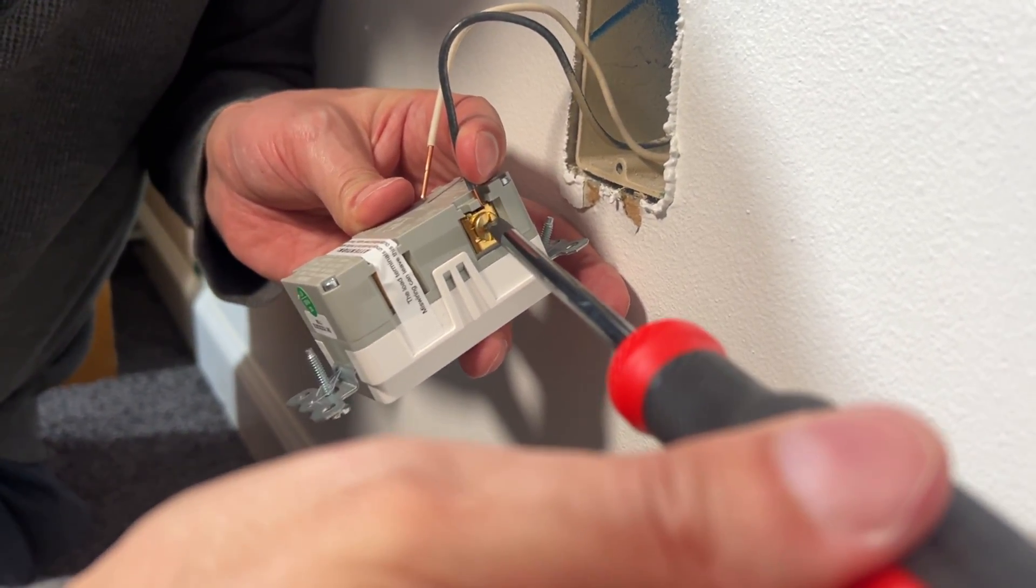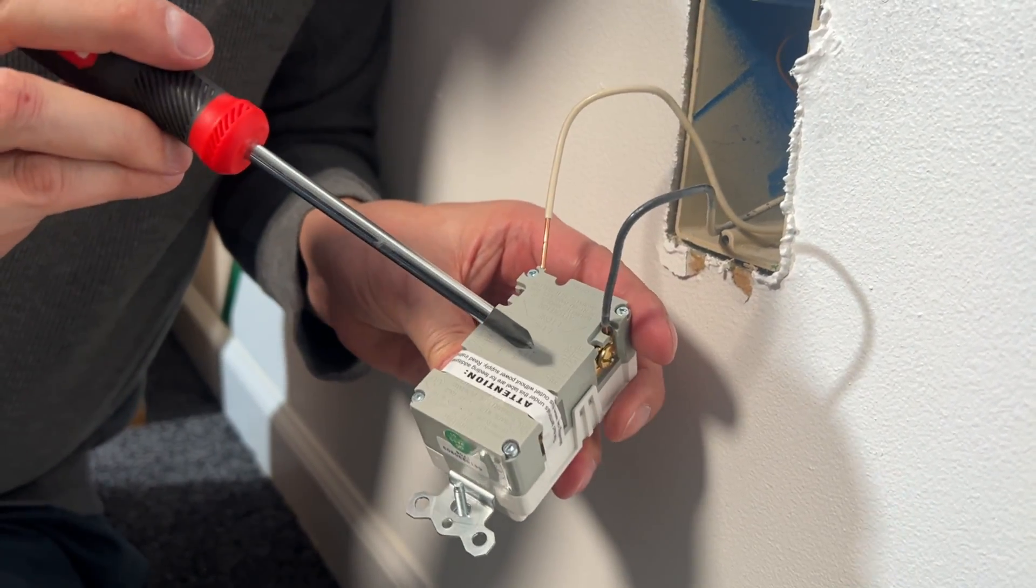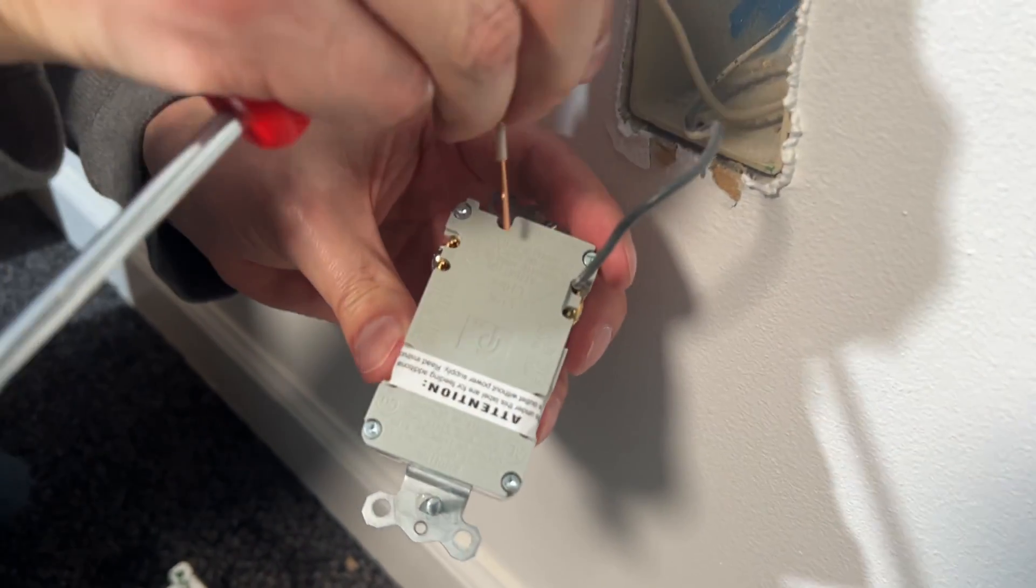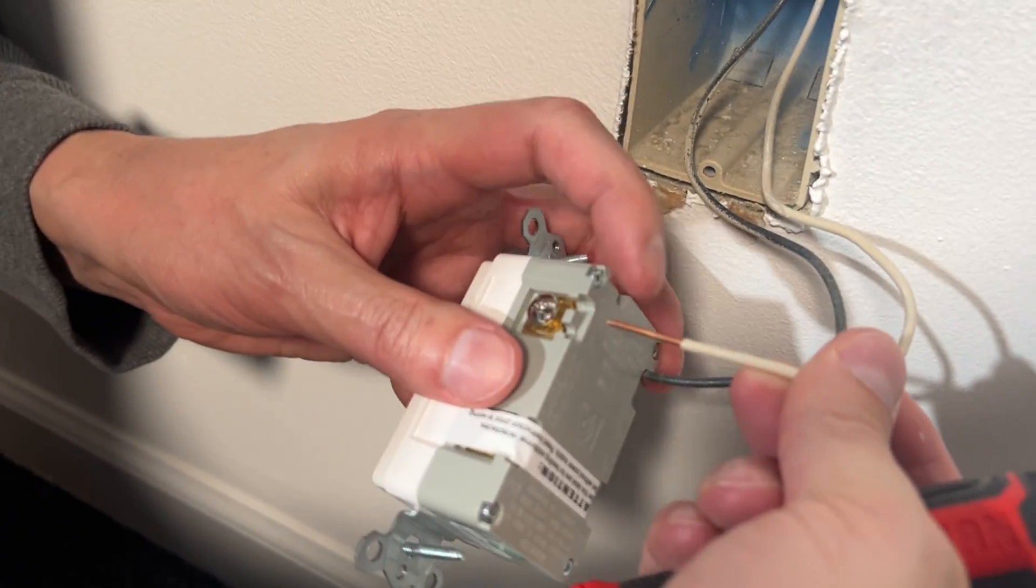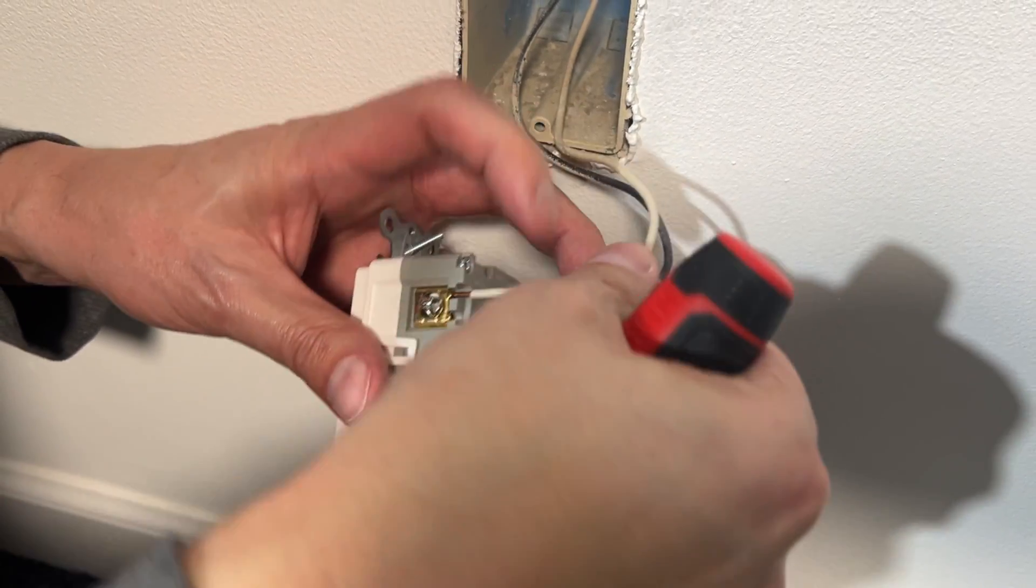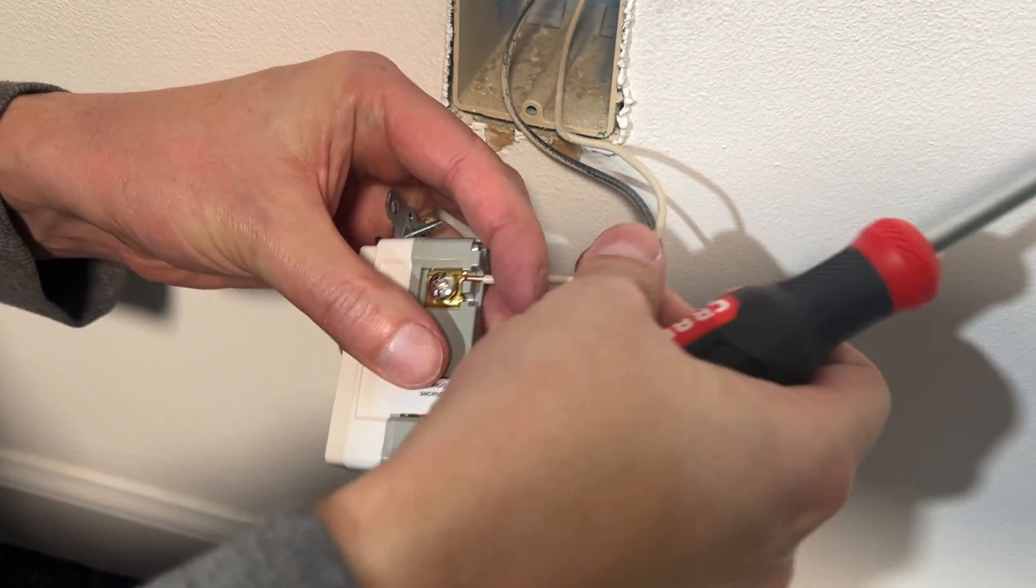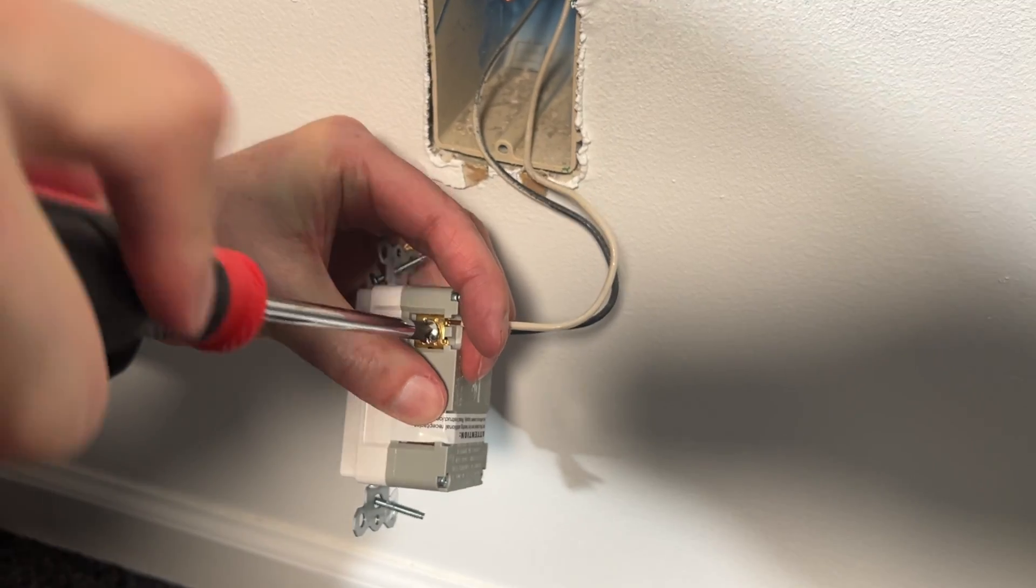On this one, it's the end of the line. We just have one outlet, and it is clearly labeled in the back. It says hot wire and white wire. Your hot wire is your black one. So it simply slides straight in. You don't have to hook the wire. If your old wire had a hook on it, go ahead and straighten it out. It goes right behind that pressure plate. All the way in. You don't want a lot of copper exposed. And tighten that on up. That's it.